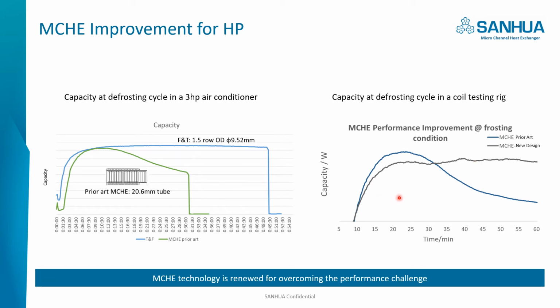And this chart is from the enthalpy loop testing. We tested the prior art design and the new design under the frosting condition. The blue one is the prior art, the current design, and the black curve is the microchannel new design. We can see that capacity keeps flat for quite a long time.